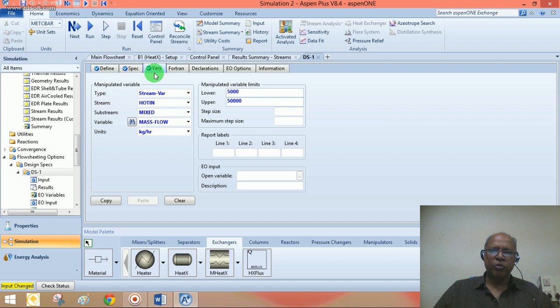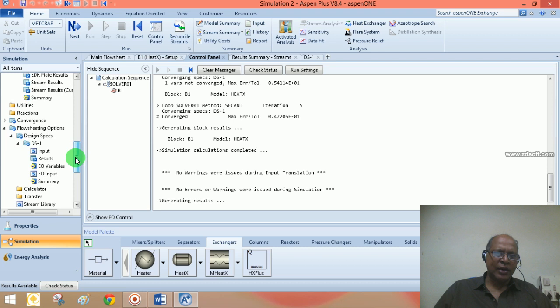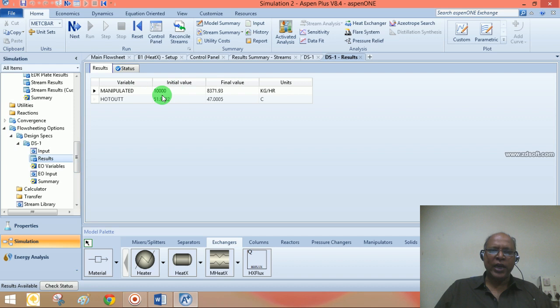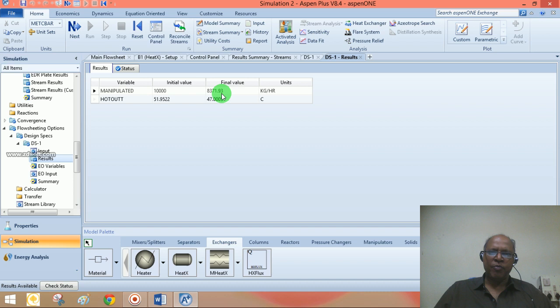Looking at the Design Spec results: starting with an initial value of 10,000 kg/hr, the hot stream outlet temperature was 51.95°C (about 52°C). When the flow rate is 8,371 to 8,372 kg/hr, the temperature is 47°C, which meets our requirement. We should use a flow rate of 8,371.93 kg/hr for the hot stream inlet. I will now copy this value and delete the Design Spec.